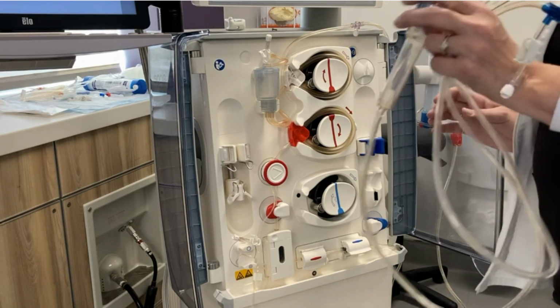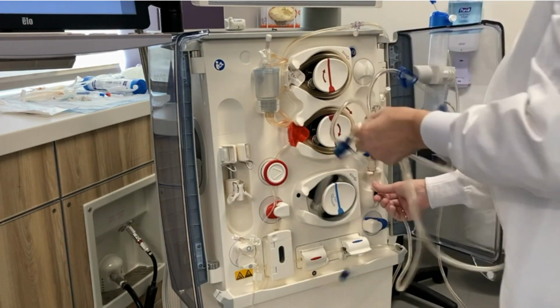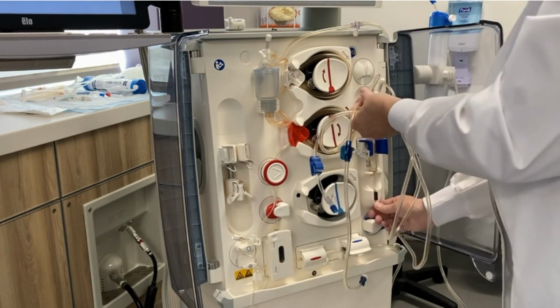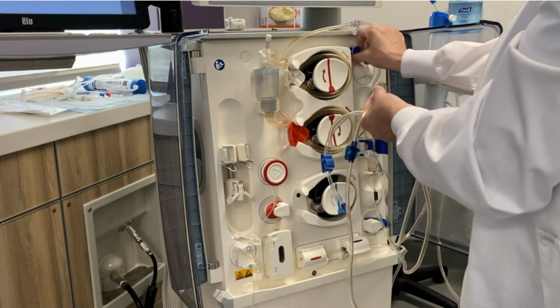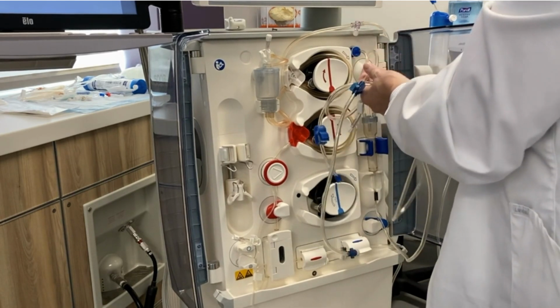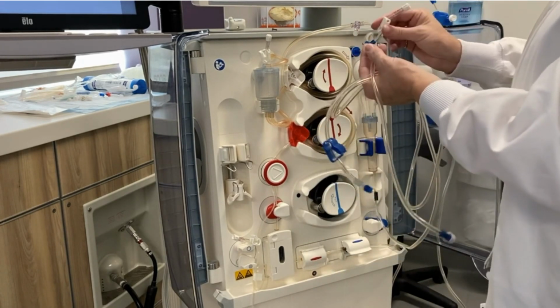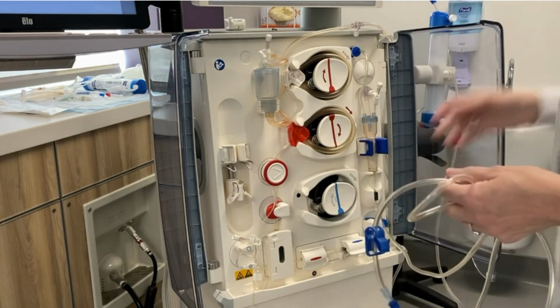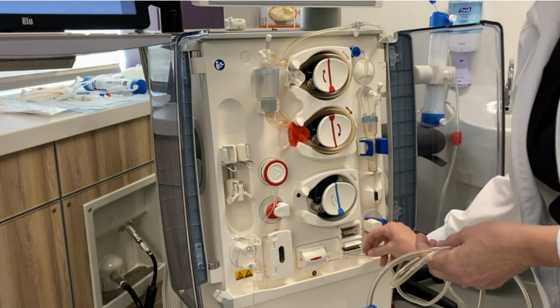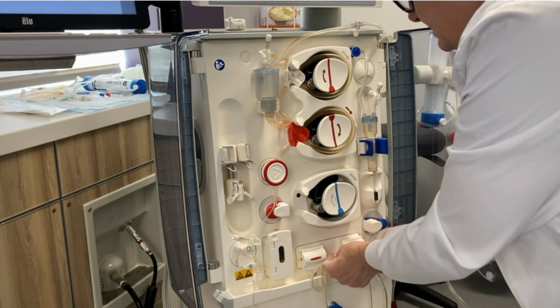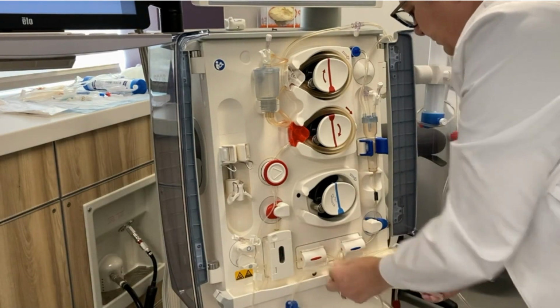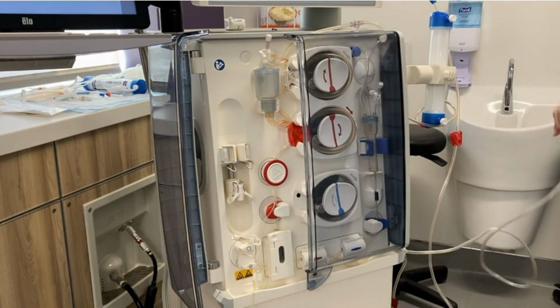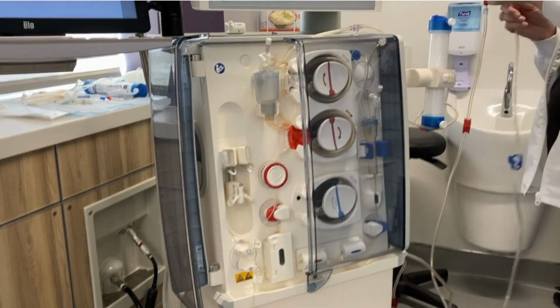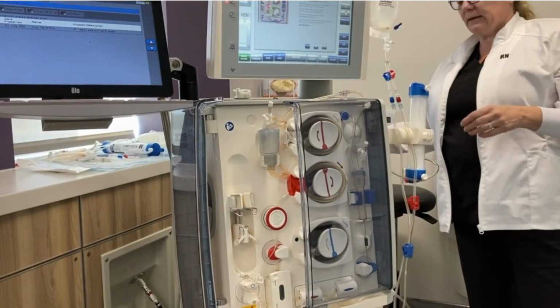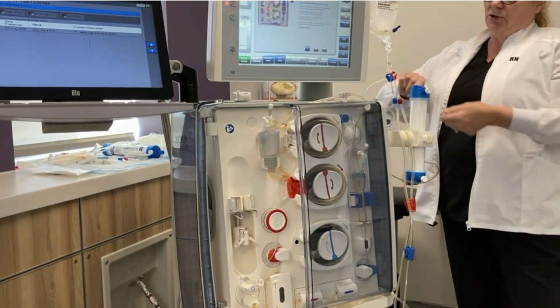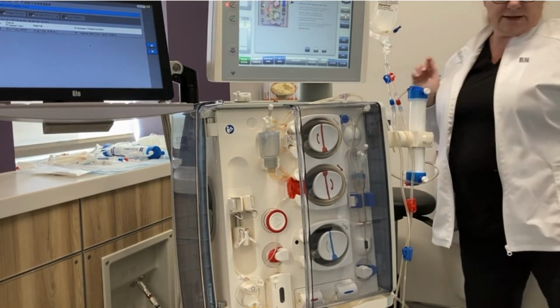So the next thing we're going to do is put the venous side of the lines up. So we put the venous bulb in, making sure to set that into the eye. Connect your transducer. Make sure your clamp is on, and another clamp on the venous line. This goes into the venous clamp and to the venous temperature monitor. And put this up to the drain bag. Attach my venous line to the dialyzer.